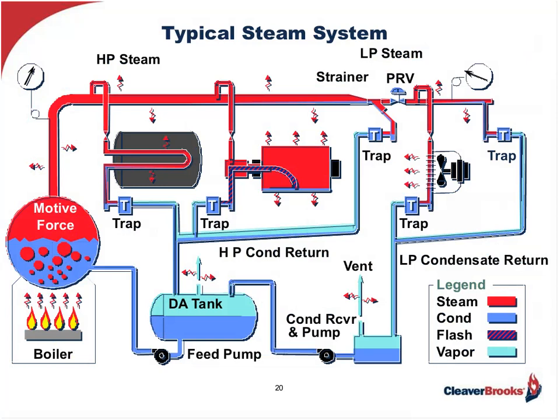So far we've addressed the boiler and some potential piping losses. For my money, I'd be looking at my condensate return system. Keep in mind the condensate is nothing more than the steam which has done its work, given up its latent energy, gone back to the liquid state, and contains a ton of BTUs — what we refer to as sensible energy. That's the energy required to get the pound of water saturated to the point where any further BTU input will cause a phase change and turn it to steam. We want to save as much of this sensible energy as possible; the higher the temperature, the better, because it means my burner has to do that much less.